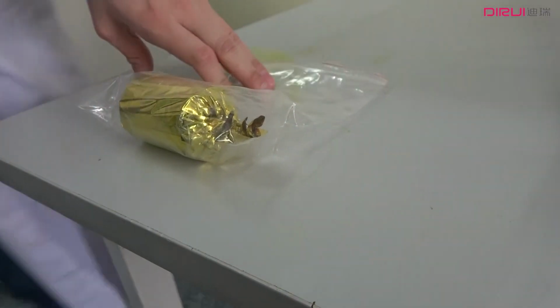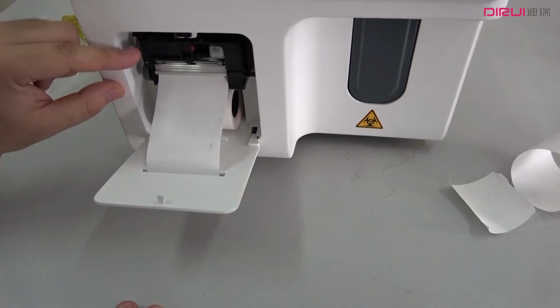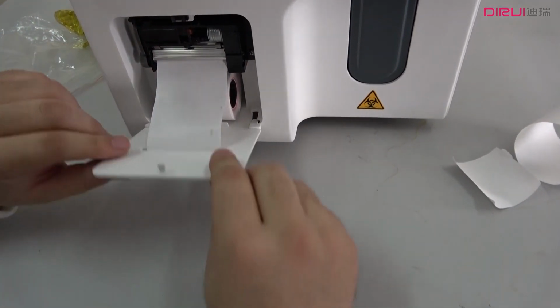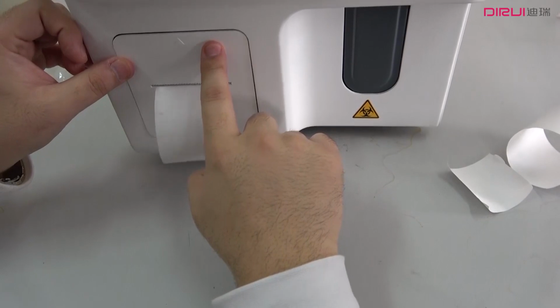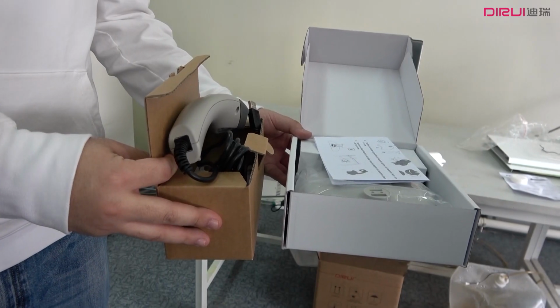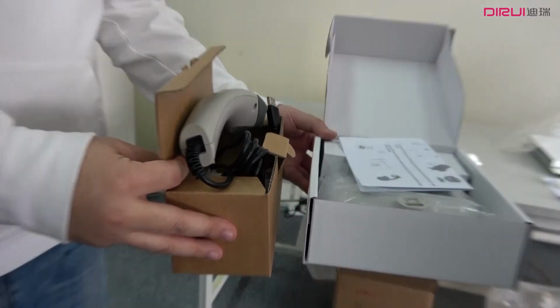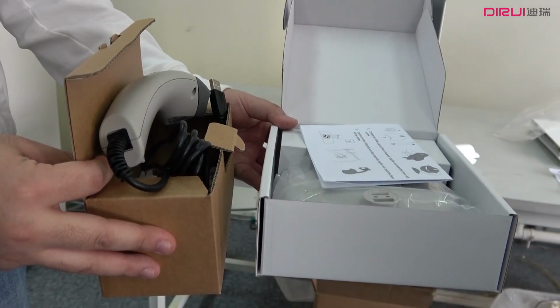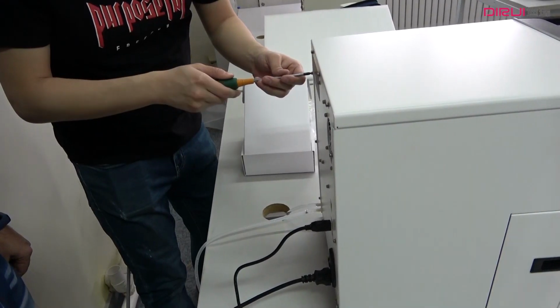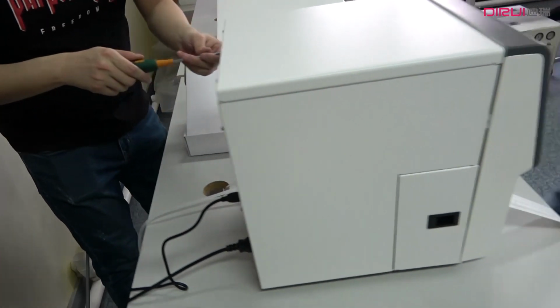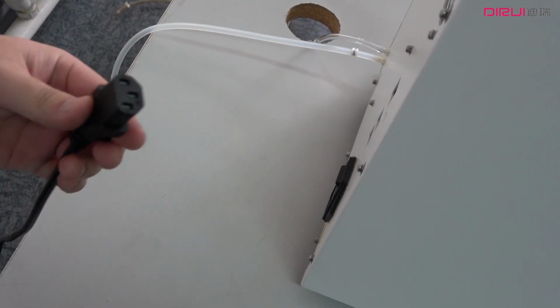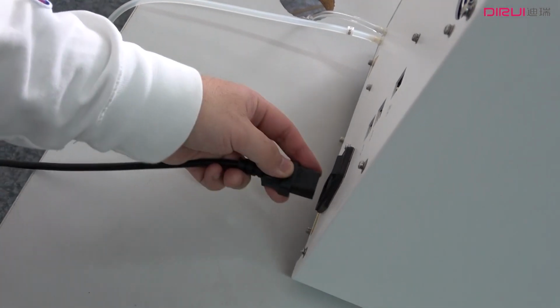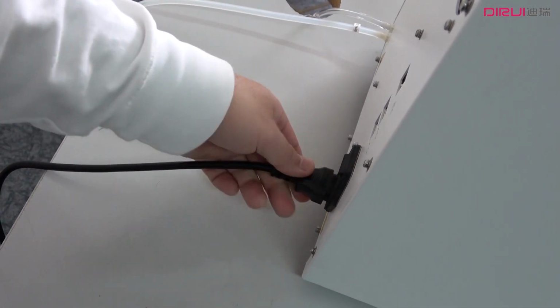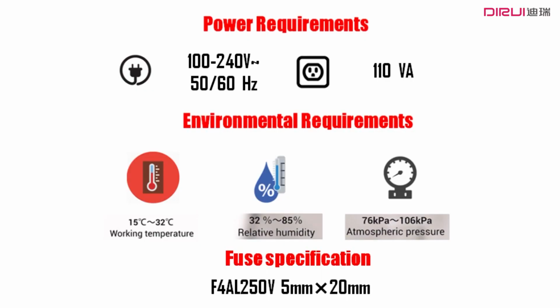Take out the printer paper roll and insert it in the printing area. Please take out the scanner box and connect the scanner base. Install all the covers back and tighten all the screws before turning on the instrument. Take out the power supply cable and connect it with the instrument. Before turning on the instrument, one must follow requirements for power and environment. Please follow this picture for detailed instructions.